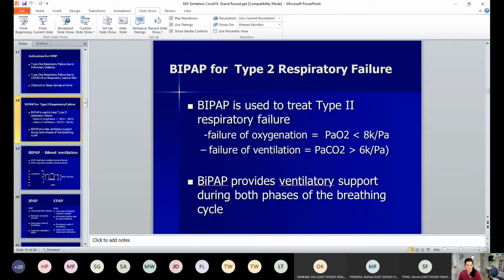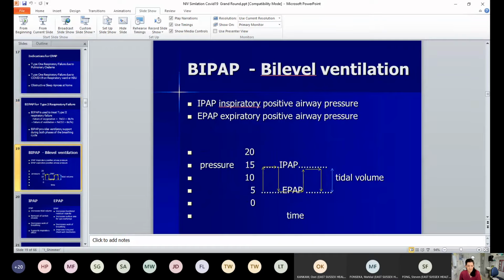BiPAP is bi-level ventilation, and it's used for type 2 respiratory failure, so when there's a lack of oxygen and a failure of ventilation. And it provides this ventilation through both cycles of the breathing cycle. So IPAP is the inspiratory positive airway pressure that boosts the patient's tidal volume as they take a deep breath in. The ventilator will give the patient a sort of support to every breath they take. And the expiratory pressure is the pressure they feel as they breathe out. So there's always some air being pushed into the back of the throat and into the alveoli, forcing the alveoli open and improving oxygenation. But the difference between the two, the IPAP and the EPAP, is the tidal volume.